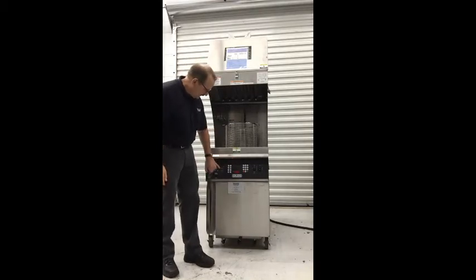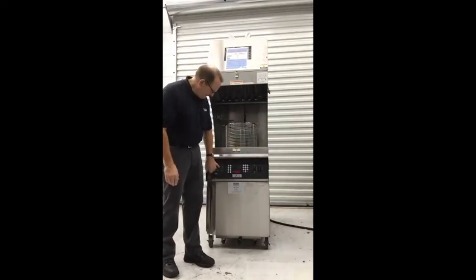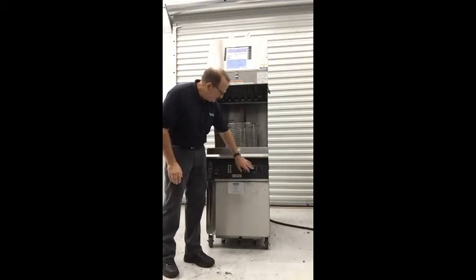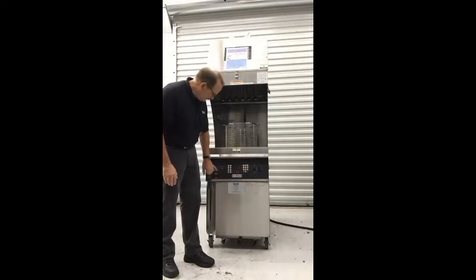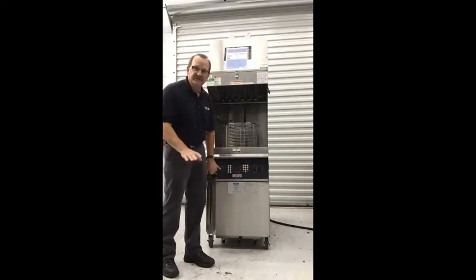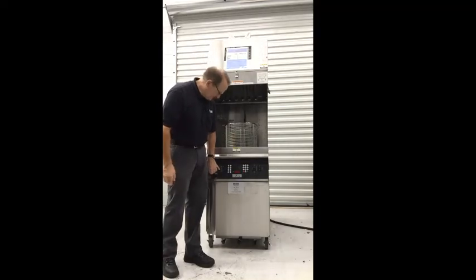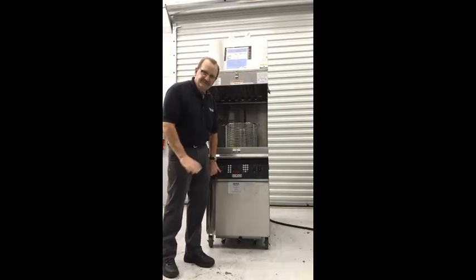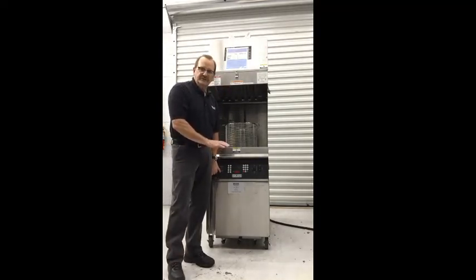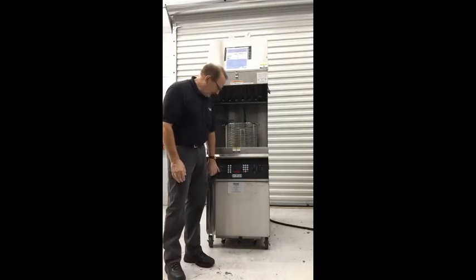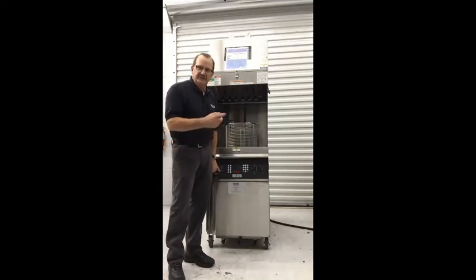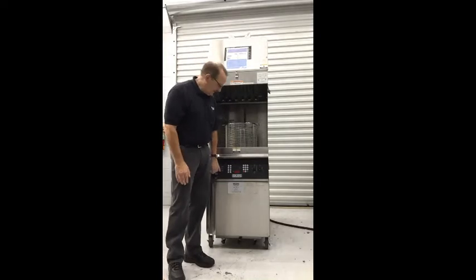We have our power, heat, high limit lights. During normal operation, the power light will be on. The heat light should accompany this. Every time this heat light over here is on, if this is in the cook position, you'll see this orange light come on, signifying that we have power to the heat contactor. And then the high limit. If the machine gets over 450 degrees, the high limit module will react. It will turn this light on and drop out the safety contactor in the back.